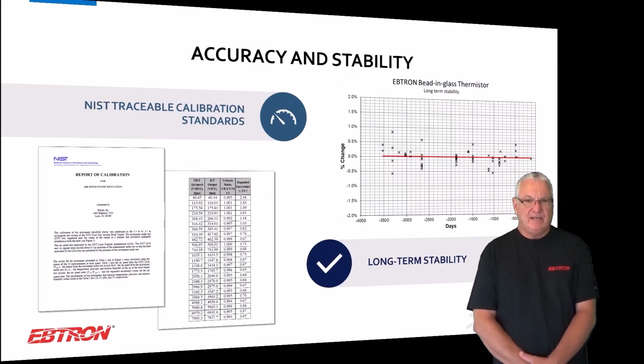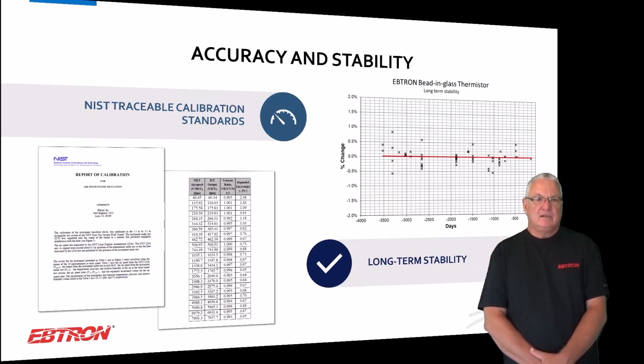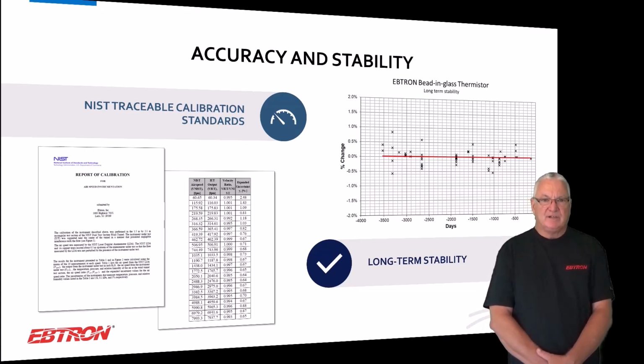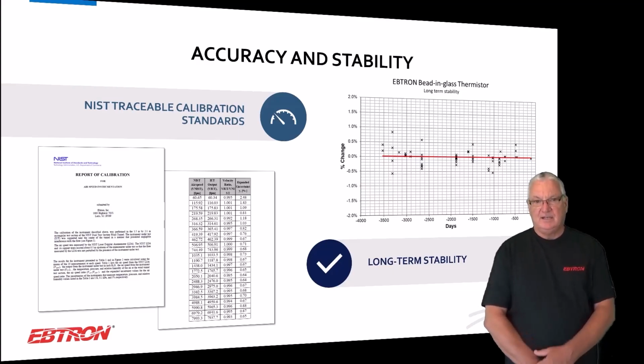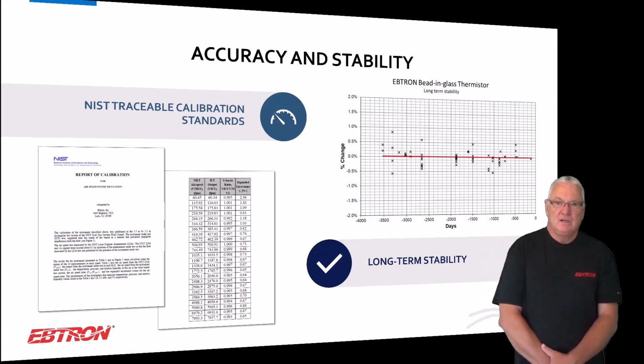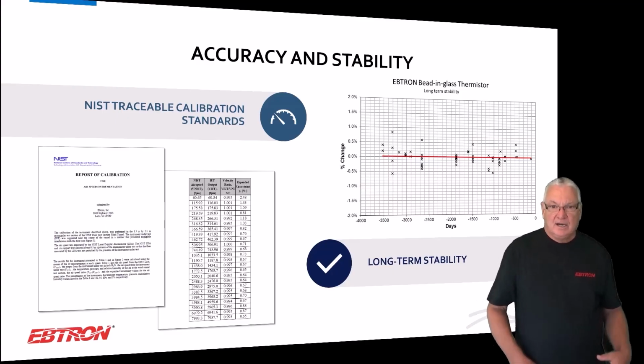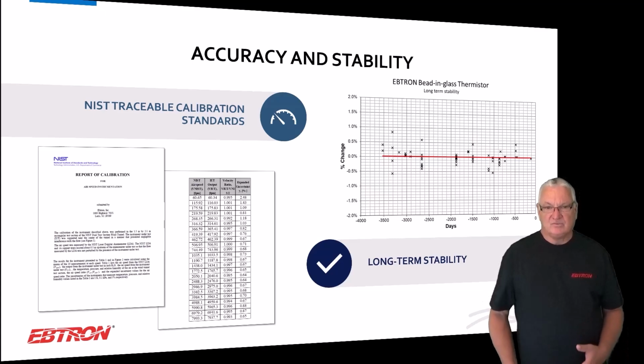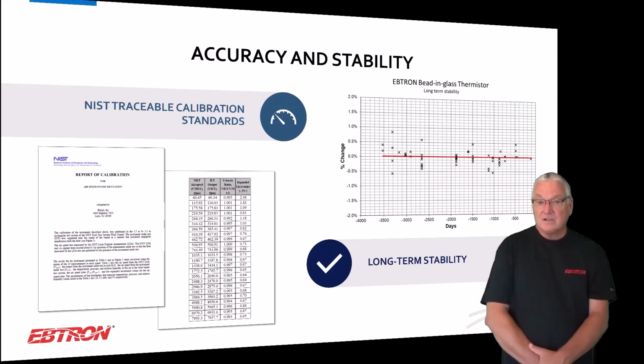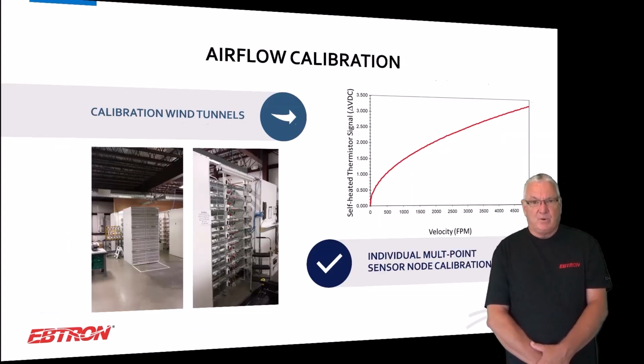Accuracy and stability. We take our Cal standard directly to NIST. We actually accompany it. They give us a report on calibration. We take that standard and transfer the calibration to our production tunnels. The stability part, kind of hard to see there on the right, but that's a 10-year study of resistance temperature characteristics of our part. So what we see is that red line is the statistical best fit line through that data set. We have no statistically significant change in electrical resistance of this part over 10 years. I could tell you that is not the norm for thermistors, but it is the norm for ours. Okay, so a very stable part.